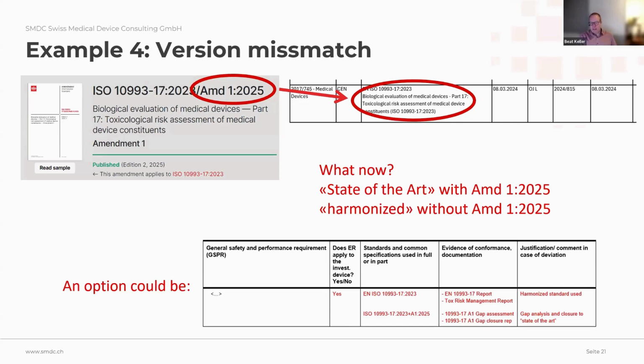What I often do is I list both. I list the version which is harmonized and the one which is state of the art, so the newest version, and I show whether there is a gap at all. Sometimes, especially in corrections and amendments, which are quite small, it has no influence on your device. Then at least you can show in a gap assessment that you have assessed it and are working on it, or you don't have to work on it because it's not relevant for your design.